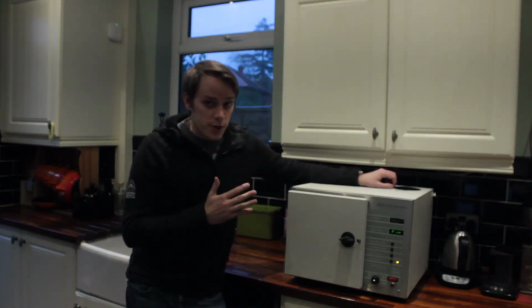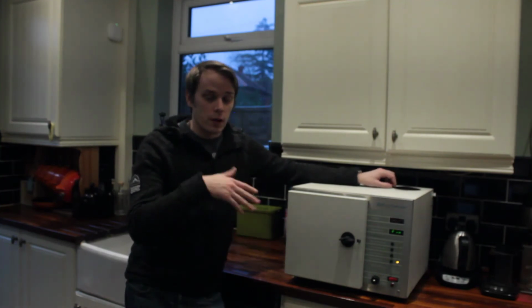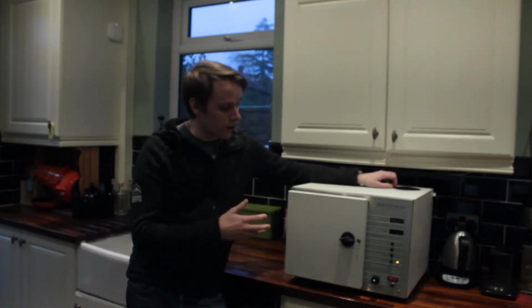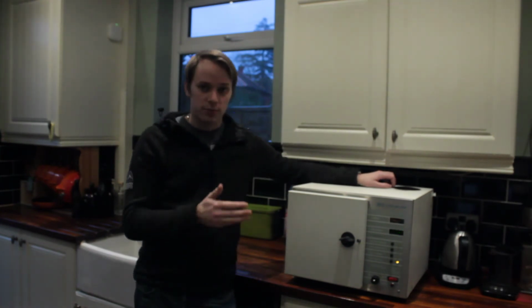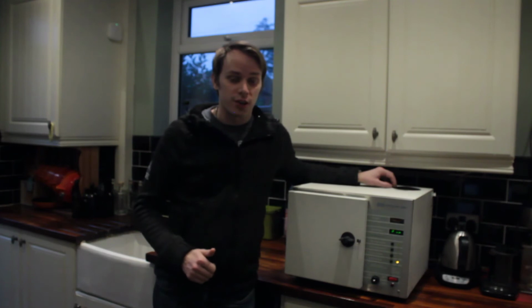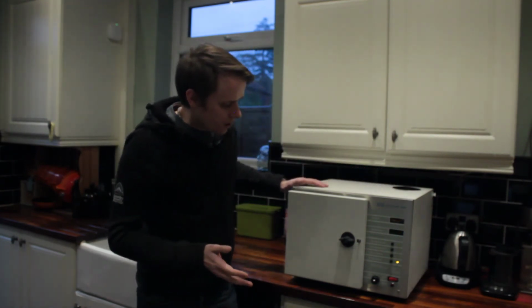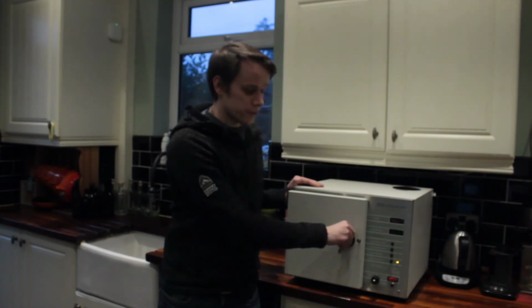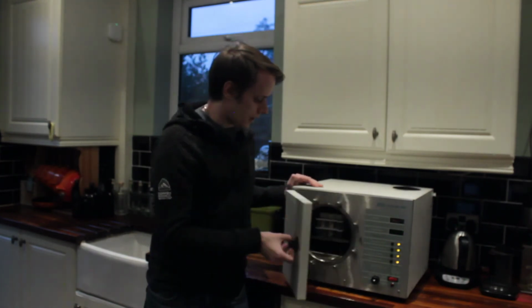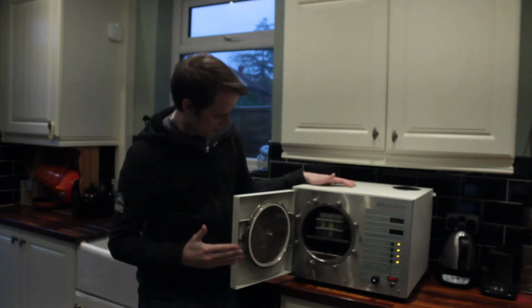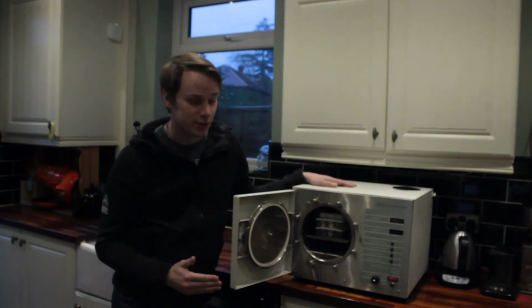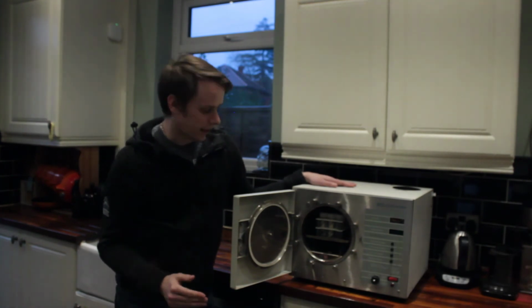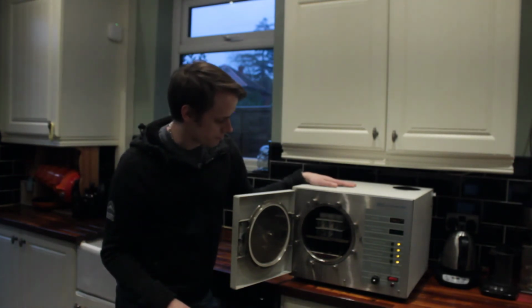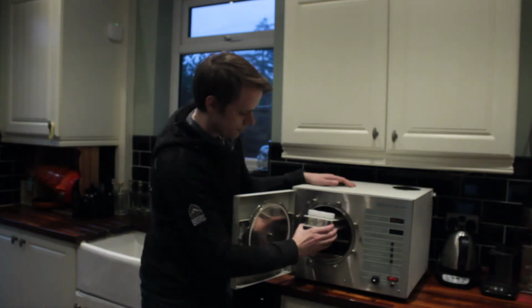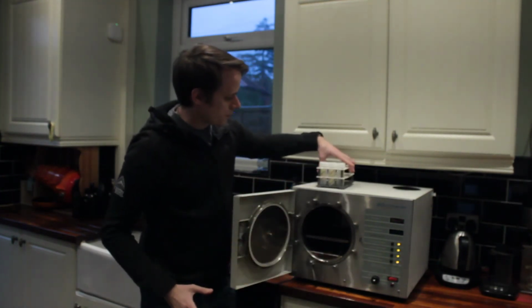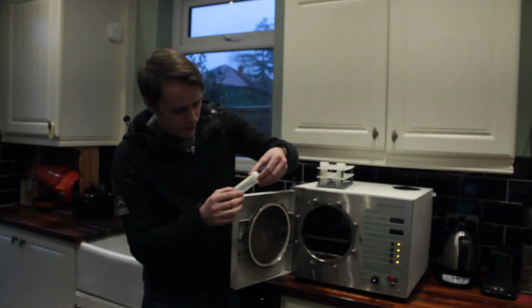Once it's released the pressure, it will go into a drying cycle to evaporate any condensed water on the inside of the chamber, and then once that's finished, it will show finished on here and it will beep to let you know. So at this point we can now open the door, unlock it and open it. And you'll notice that everything inside is still very hot, so you want to be careful removing anything from the autoclave at this point.